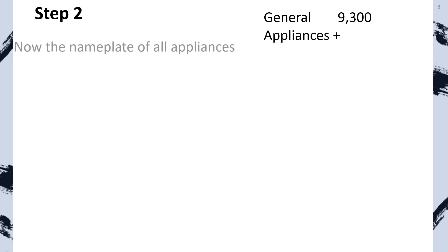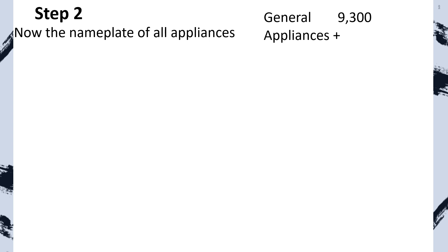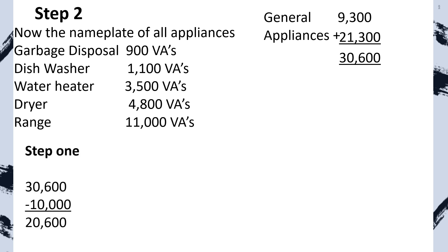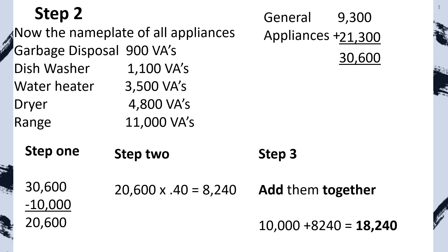Now find the nameplate rating of all appliances — they're listed out here. We total them together and that equals 21,300 VAs. Total those two together and now we're ready to apply our demand factor to this portion of the load calculation. We take the first 10,000 at 100%, take the remainder at 40%, and add them back together. Now let's go do our HVAC.